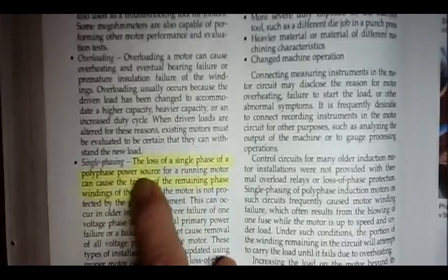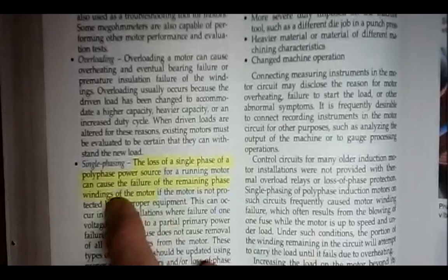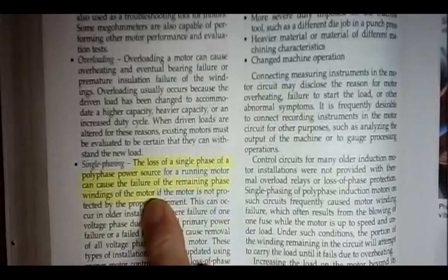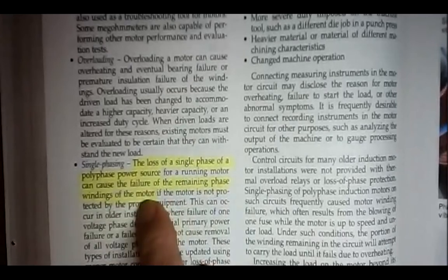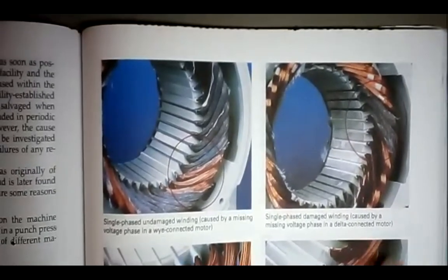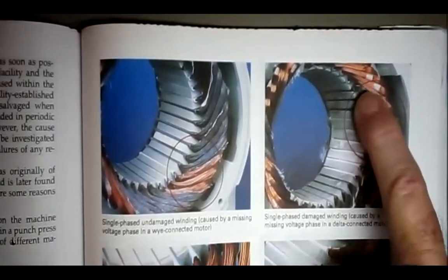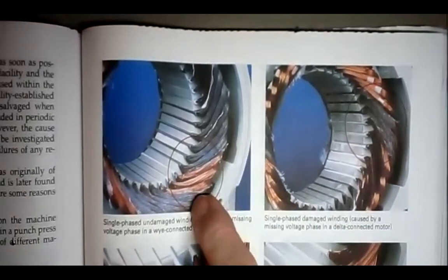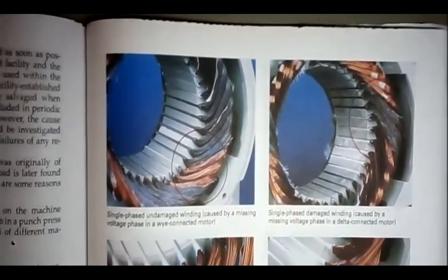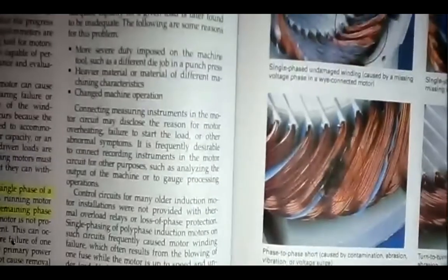The loss of a single phase of a polyphase power source can cause the failure of the remaining phase windings of the motor because they're going to have a higher current on those two windings, and the overloads won't detect it. And over on page three, they're giving us some photos of actual damage of a motor that was running in single-phase condition, a three-phase motor that was running with just two of the three phases. It was single-phase motor, so those windings have gotten burned up.